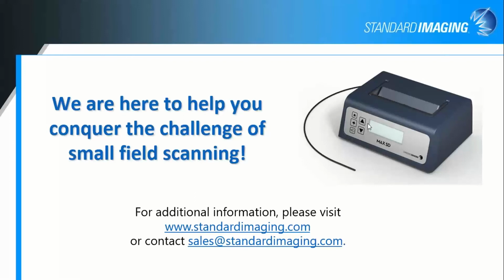Let's see, I see another question. Is a reference detector needed or advised during scanning for the scintillator? Because you're scanning so slowly, you really don't have to have a reference detector. You certainly can if you'd like. I know some systems don't really allow you to scan without, but a single pulse on one end or the other doesn't affect the overall signal magnitude nearly as much as it does in your really short measurements when you're scanning quickly. So no, you do not have to have a reference detector when you're scanning with the scintillator.